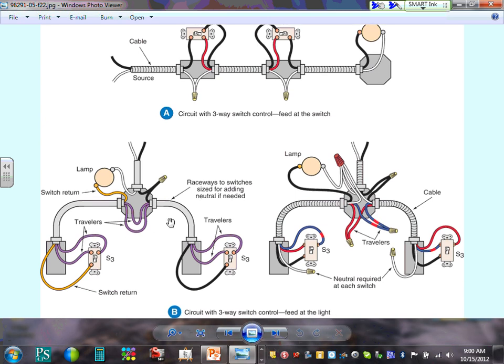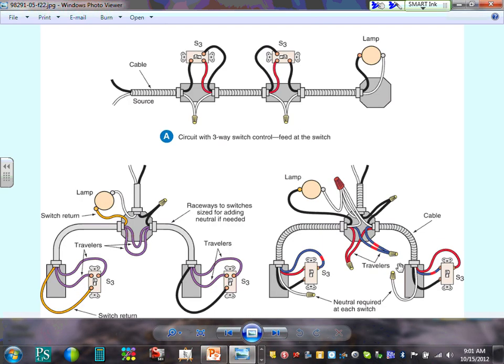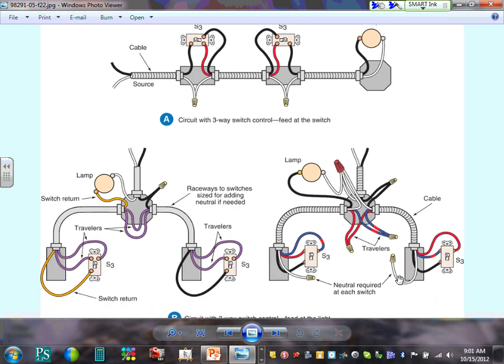Here's a wiring method where you bring the service into the switch circuit, and here's where you bring it with a cable. Can you see that when you bring it with a cable, you need a neutral? This is great for estimators. If you're using an MC cable and you don't know that if these receptacles are for light, you have to bring another wire based on 2011.